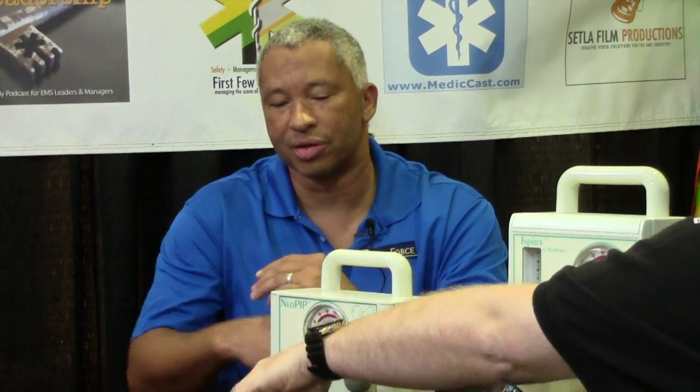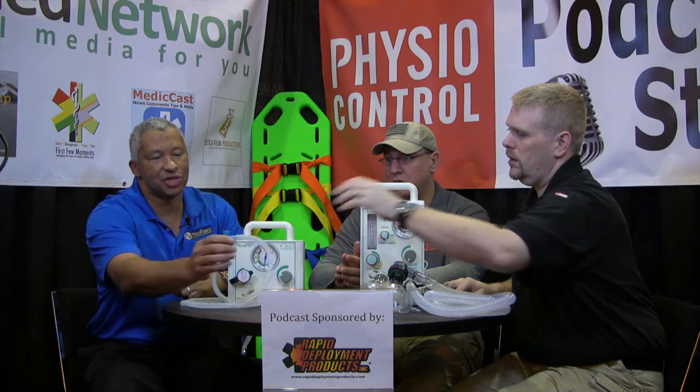Well, thanks, Kyle, for having us here. The difference between a manual resuscitator and a ventilator is the ventilator is a little bit more complicated, and you can set volumes as well as pressures. A manual resuscitator is basically a very simple device. It's a pressure control device that we've developed for both neonatal and pediatric adult populations. What we do is we very precisely inflate the lungs to a very precise pressure. So this is a T-piece circuit here. There is a constant flow through the device. We occlude the circuit, and then we adjust the pressure to about 18 centimeters for babies.